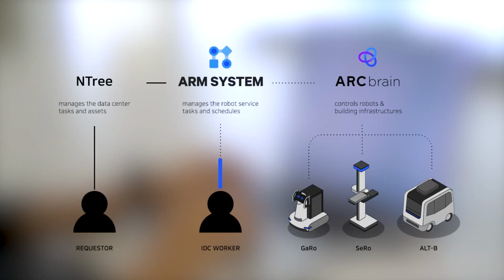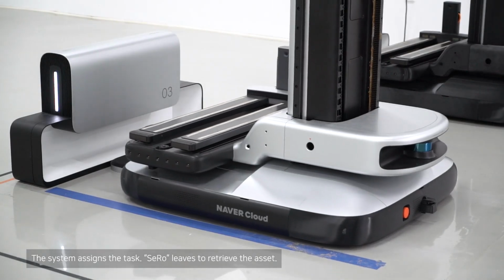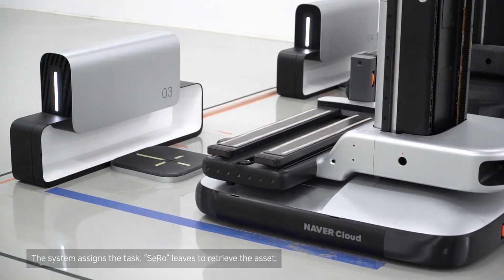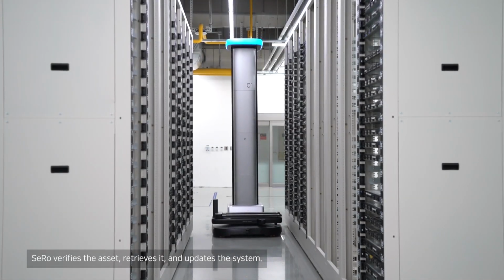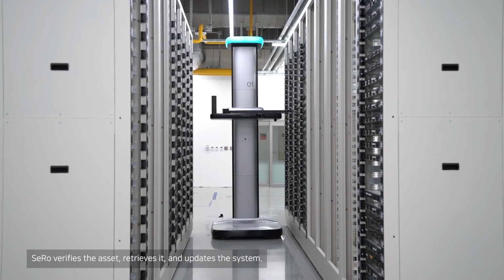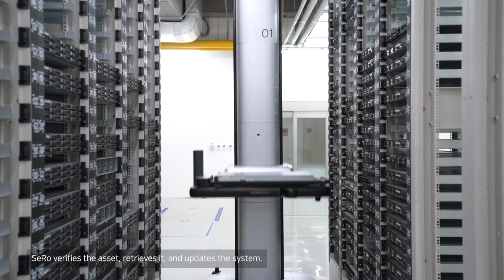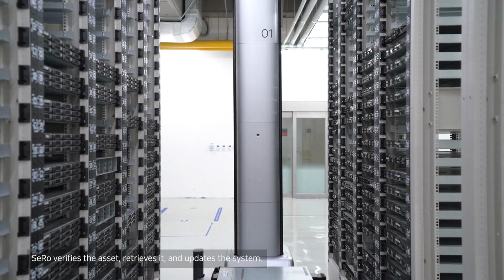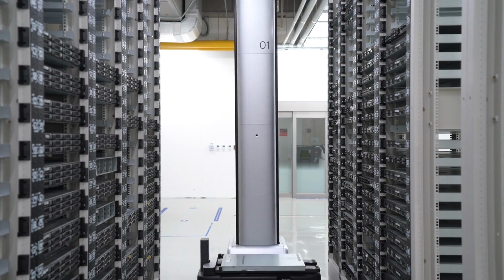Once a task is registered, the robot system assigns it to an available robot. SeRo, an asset management robot waiting at the charger, departs to retrieve the asset. SeRo moves to the rack with the registered server, uses OCR to verify the asset number, and retrieves the server. After a successful retrieval, the robot system updates the asset records automatically.